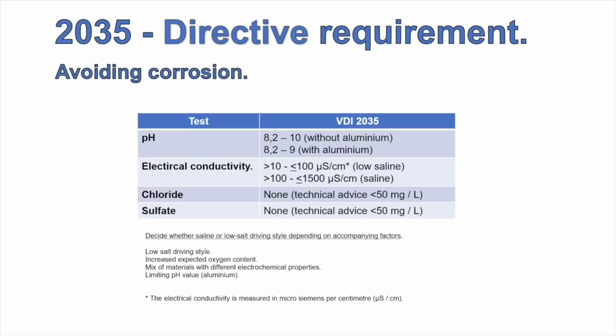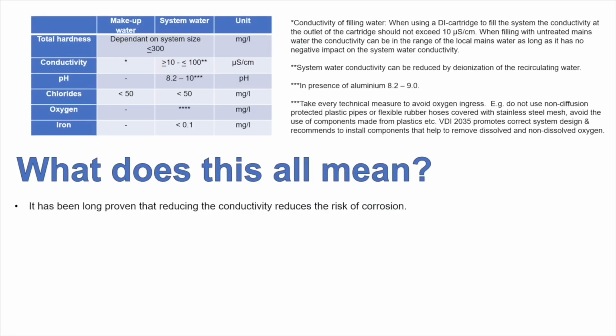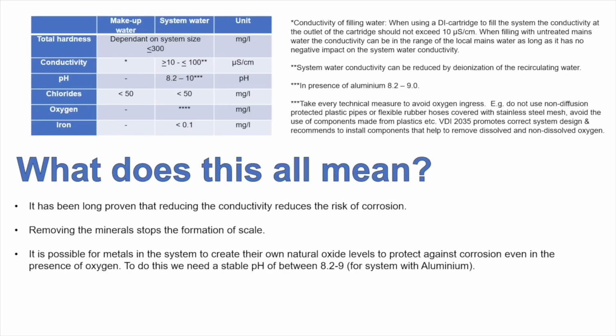The 2035 directive is very simple to follow. This table shows what we're looking for in terms of pH, electrical conductivity, chloride and sulfates within our system. If we achieve these, we will create an environment where corrosion cannot take place. What does this all mean? It's long been proven that reducing the conductivity reduces the risk of corrosion. Removing the minerals stops the formation of scale. It is possible for metals in the system to create their own natural oxide levels to protect against corrosion, even in the presence of oxygen.